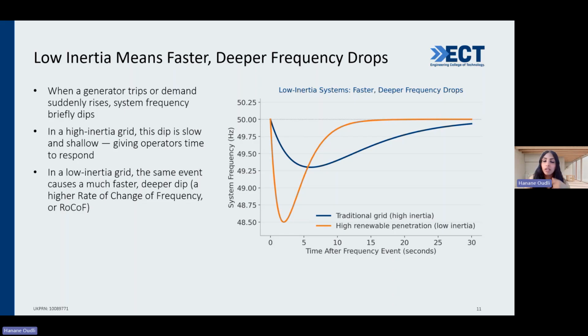In high inertia systems, as you see here, the navy line is for the traditional grid with synchronous generators, and the orange line is for renewable penetration. In a high inertia system, the stored kinetic energy in synchronous machines helps slow the initial frequency decline. The frequency still changes, but the change is more gradual. In a low inertia system, the orange line, the same disturbance can produce a faster initial frequency change. One important metric here is the rate of change of frequency, ROCOF, which tells us how quickly frequency is changing.